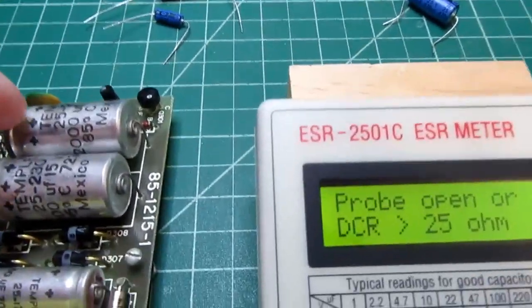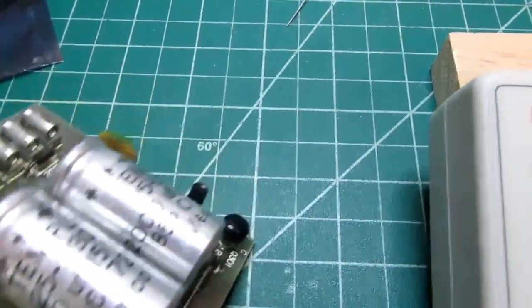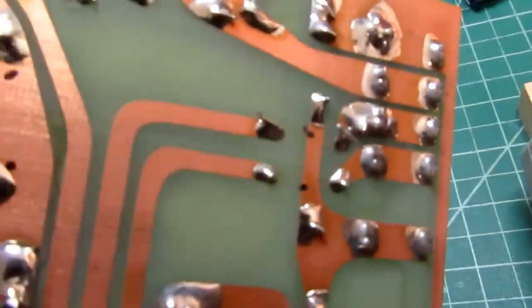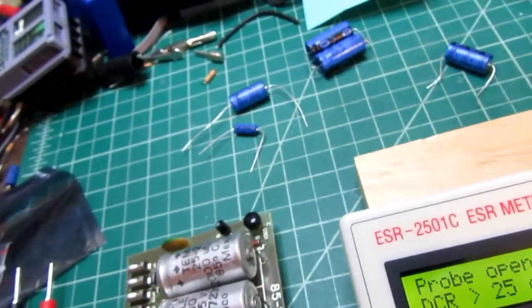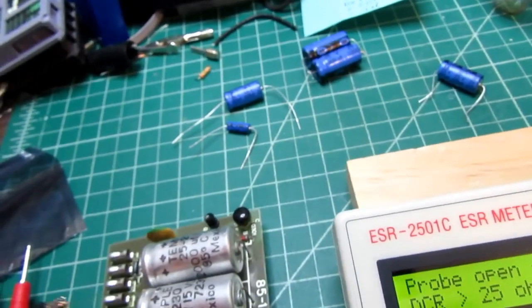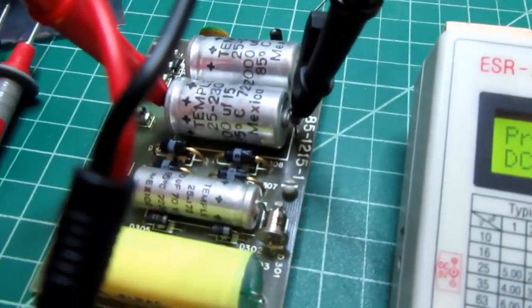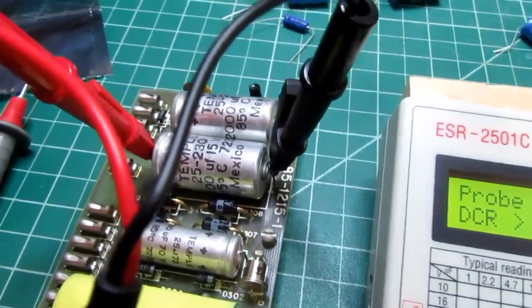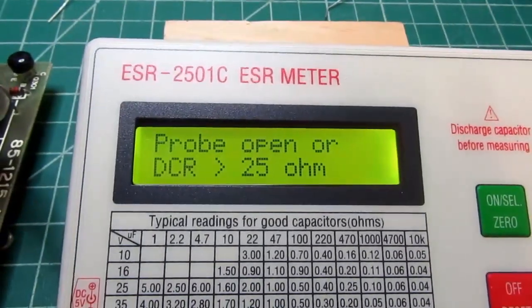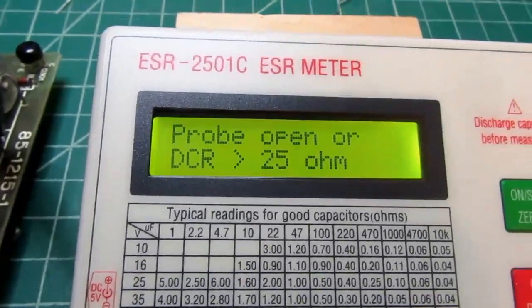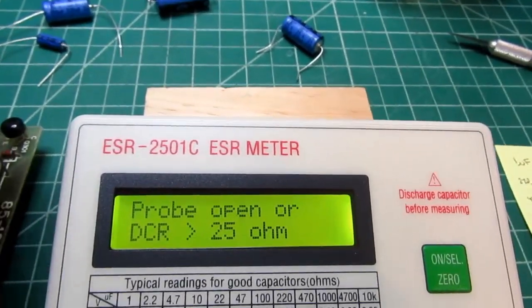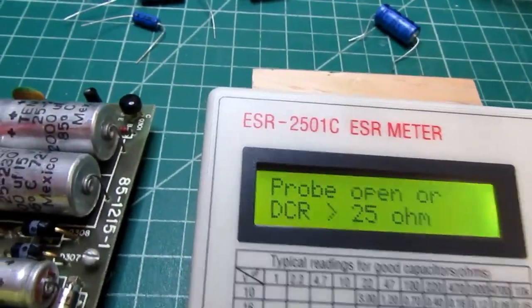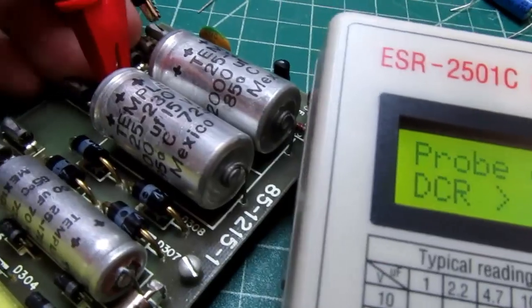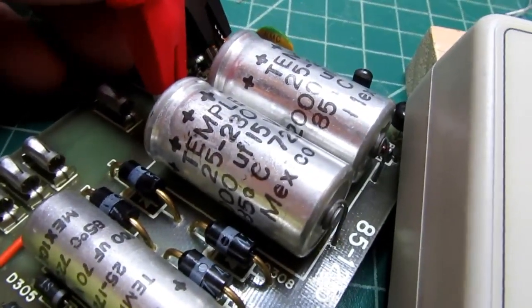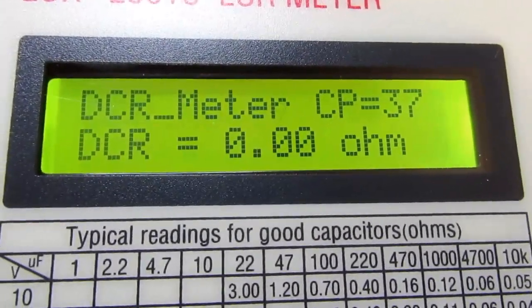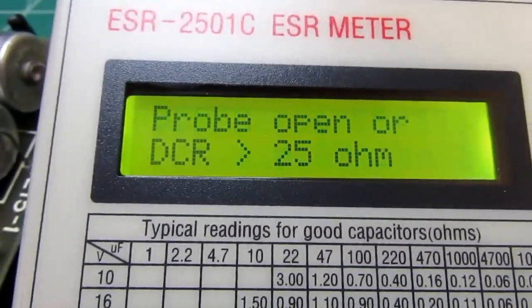Now these are two capacitors of 2,000 microfarads each, paralleled on the circuit board, so it's really 4,000 microfarads. I need to short this out first. Alright, I've got the test leads clipped onto the paralleled capacitors, and it's giving me a DCR of greater than 25 ohms, so that's good — but is it really good, or is it lying to me? I'll clip onto the lead of the other capacitor, which I know is electrically common, and it does reflect that the DCR is 0 now, so that confirms it was a good DCR test.